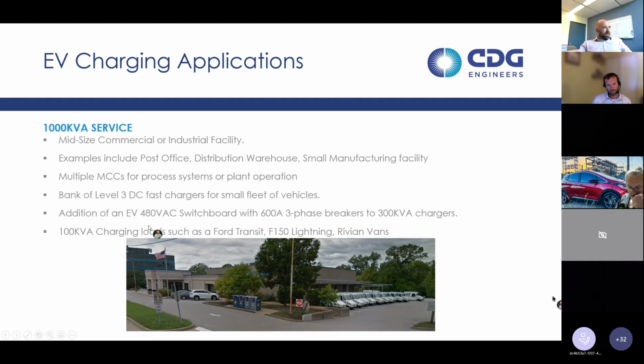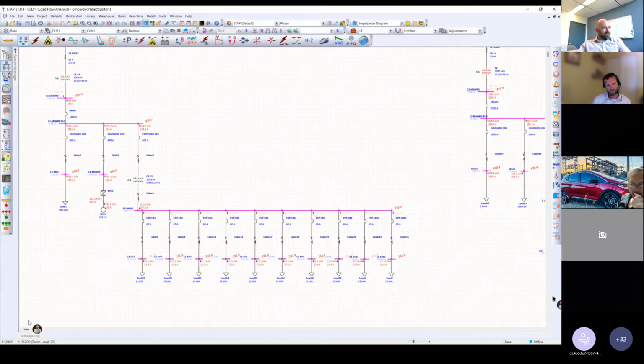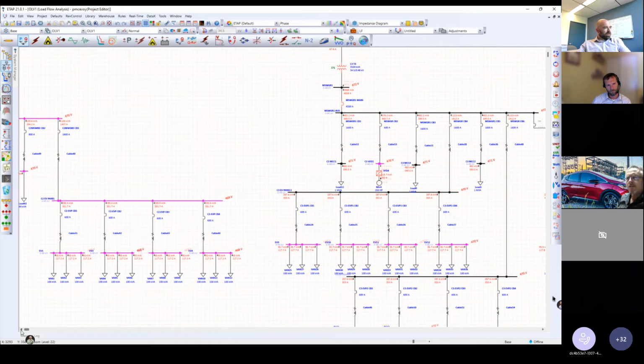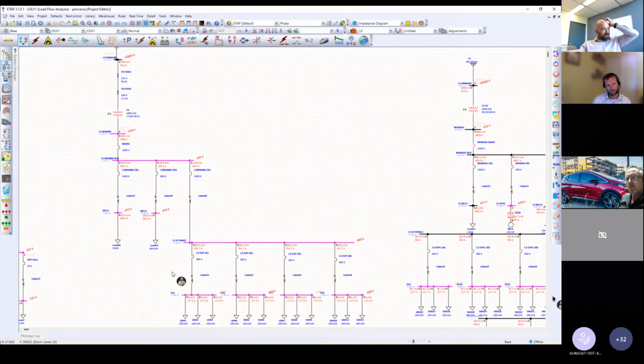So we suppose they put in a 480-volt switchboard with 600 amp 3-phase breakers to power a 300 kVA EV charging station that might handle 2 or 3 vans at the same time. Charging load would be about 100 kVA, such as the Ford Transit, an F-150, or a Rivian van. What that looks like in a one-line is nothing too crazy, just a bit bigger than what we were showing before.